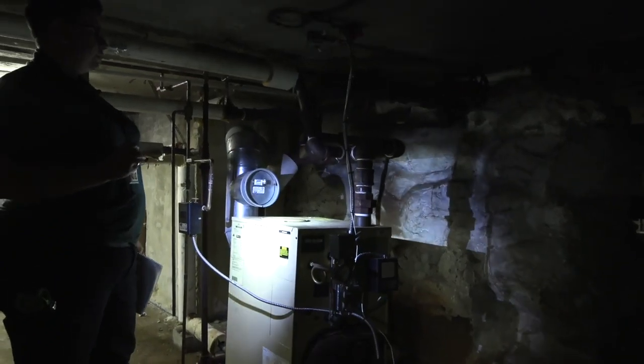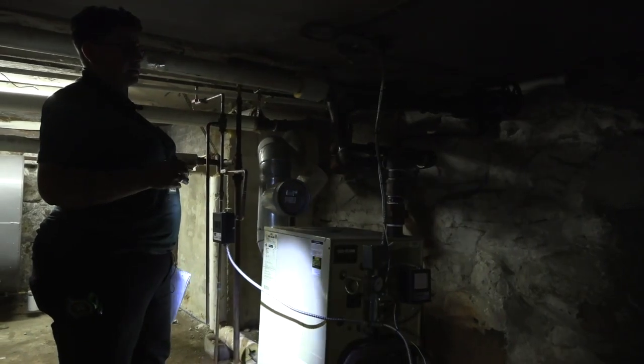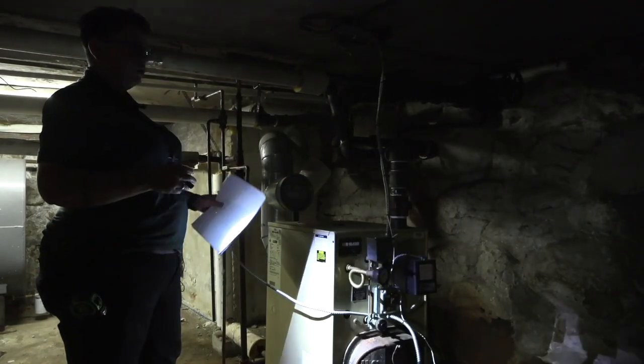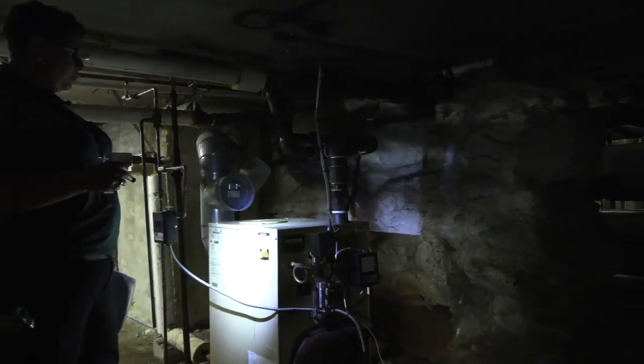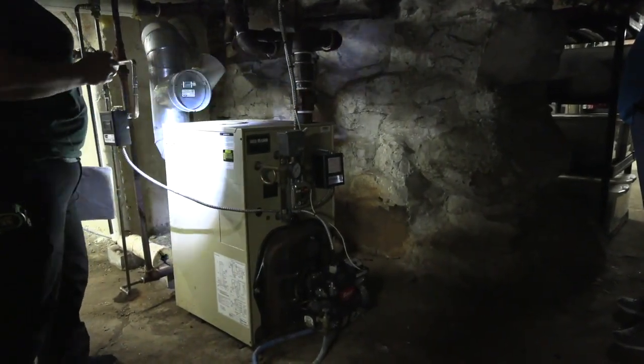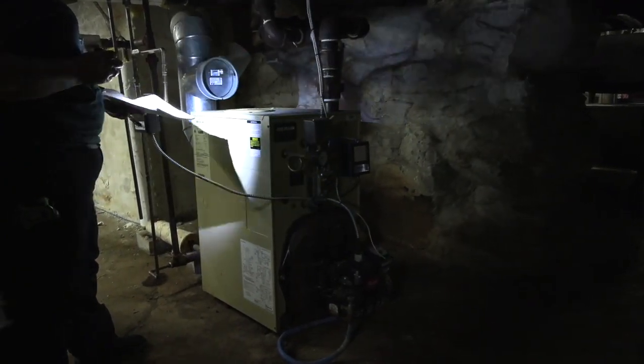The boiler itself isn't too incredibly old and it has a newer burner. Oil burns a little bit dirty so having it serviced every year is a really good idea. Ideally if we get you set up with heat pumps you'll be relying on this a lot less, if at all. Heat pumps can in fact be the sole source of heating and cooling for your building if they're sized correctly. A steam boiler you're really not going to get much more efficient than it is, but keeping it as a backup wouldn't hurt since it's not at end of life yet.